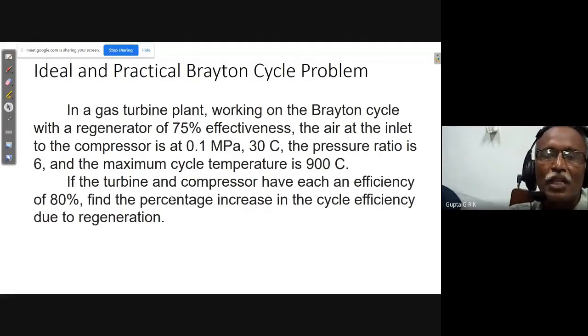And also, some typical values you have to remember. Turbine efficiency and compressor efficiency: usually turbine efficiencies are a bit high, up to 85%. Compressor efficiency will be 80% only, not more than that, while turbine efficiency may go up to 90, 93, and so on. Transmission efficiency can be up to 99%; it's very small losses, just bearing losses and so on.